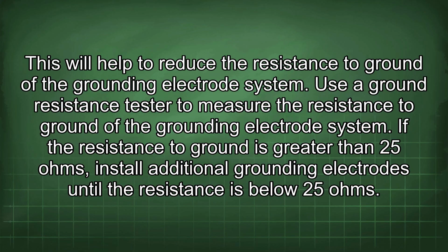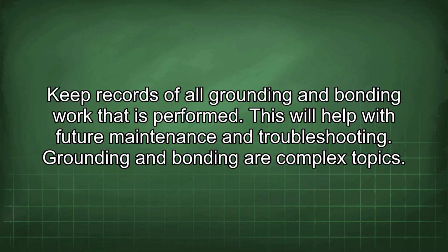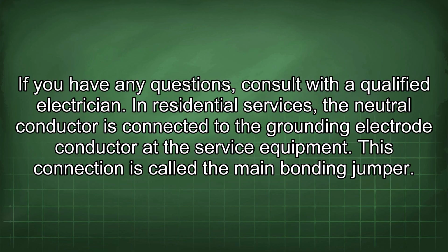Use a ground resistance tester to measure the resistance to ground of the grounding electrode system. If the resistance to ground is greater than 25 ohms, install additional grounding electrodes until the resistance is below 25 ohms. Keep records of all grounding and bonding work that is performed. This will help with future maintenance and troubleshooting. Grounding and bonding are complex topics. If you have any questions, consult with a qualified electrician.